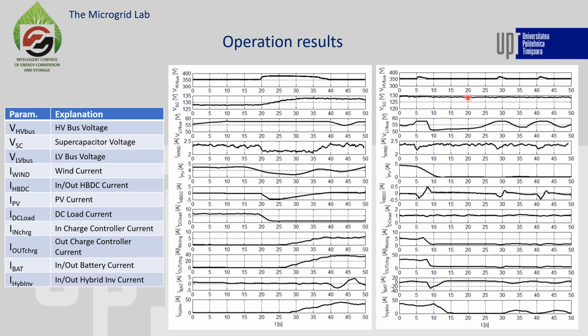The hybrid bidirectional DC converter will only activate when the voltage in the high voltage DC bus is above 365 volts. The fluctuation presented in the hybrid DC converter's current is very small and of no consequence. The actual reaction to stopping the PV system, as you can see, can be observed in the operation of the charge controller, which is decreasing the current. Due to this, the hybrid inverter will stop pumping power into the main grid and attempts to take energy from the batteries in order to compensate the energy in the low voltage DC bus.